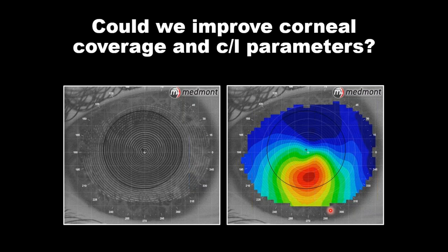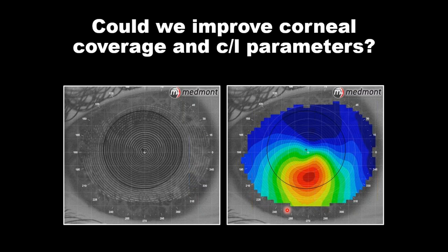One of the advantages of the Medmont is it has one of the largest areas of coverage of any of the Placido topographers, but in some irregular corneas, especially very steep corneas, we're going to miss some information — and that missing information is very valuable to us.